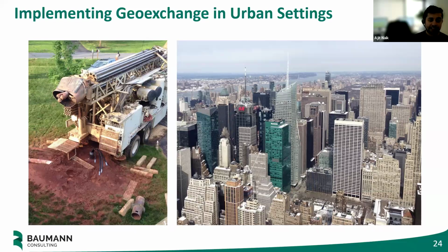At a certain point, if you put in just a gas-fired boiler, it's going to cost you a certain amount to operate. If you have the geothermal system, it's going to be cheaper. You try to balance it so that you put in as much geothermal as makes sense, balancing your first costs and your energy costs on a life cycle basis over the entire life of the system.